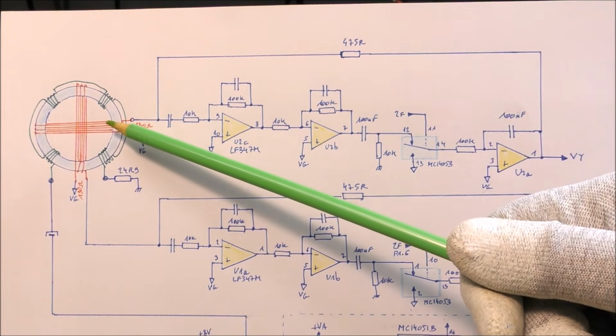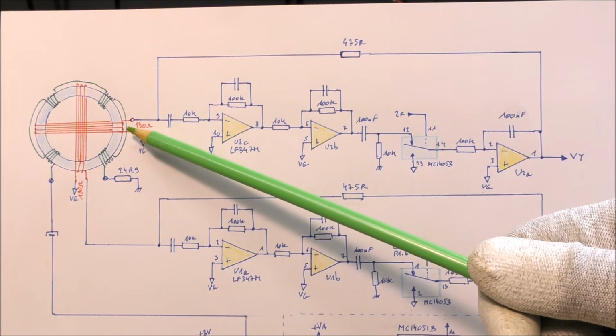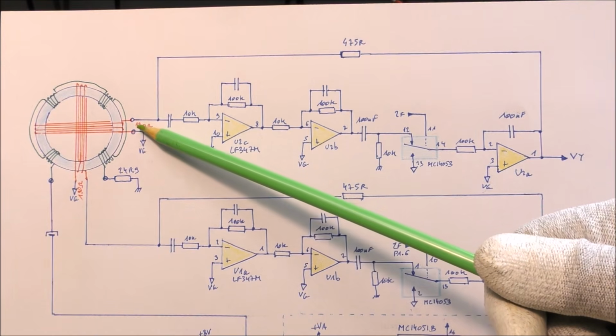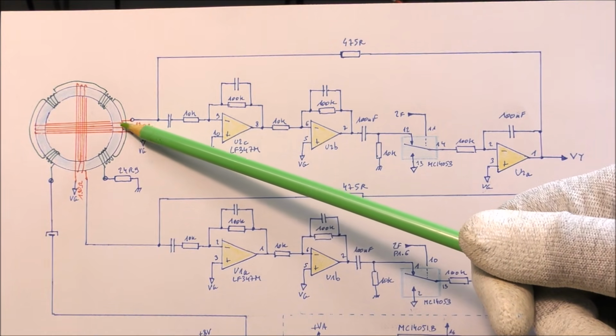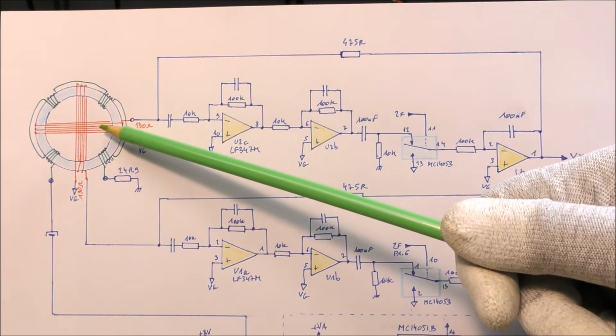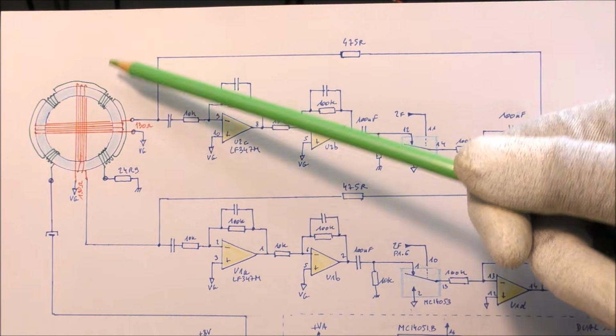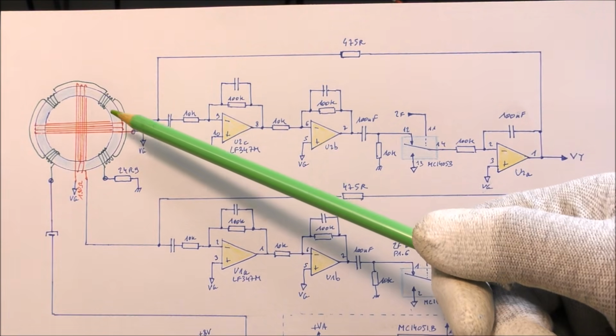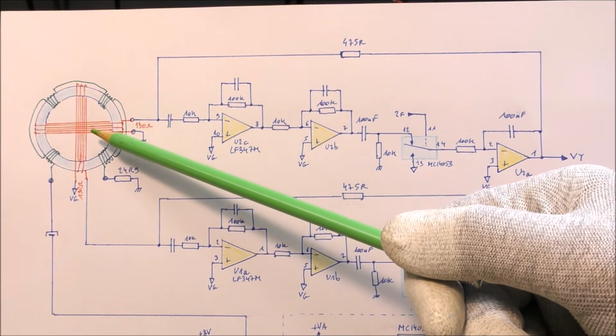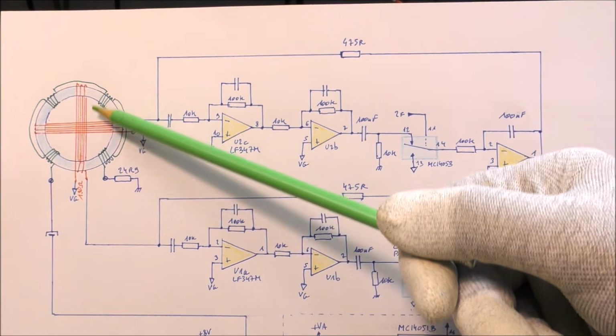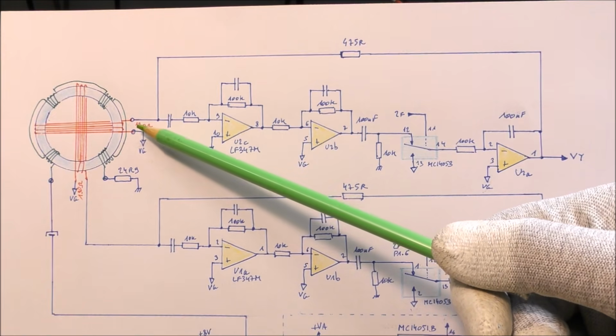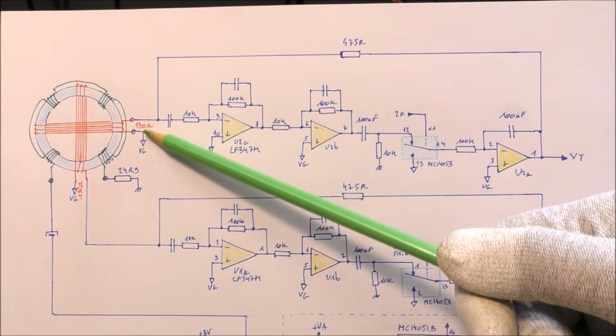Each coil has actually 2 different functions. One function is to sense the second harmonic. The second function is to generate a magnetic field which will compensate the external magnetic field. If the sum of the external magnetic field and the magnetic field generated by the coil is not zero, there is here a second harmonic signal.